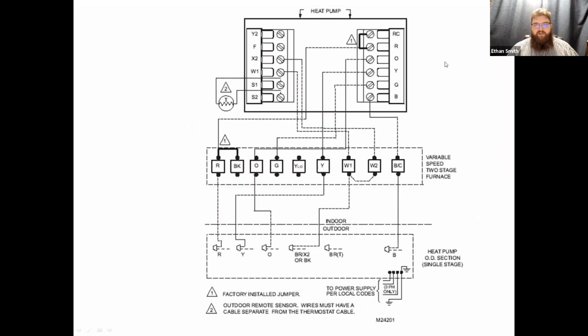Okay, so there's an example of one of these wiring diagrams for a heat pump. This came out of the thermostat wiring diagram. It's typically, like I said, the best place to go. You'll notice a couple unique things. We've got our furnace, we've got our outdoor unit, and we've got our thermostat subbase. Your O terminal is going to come off the thermostat. A lot of times it will land in the furnace, especially in the variable speed models, because that furnace wants to know whether it's heating or cooling, and then it will proceed to the outdoor unit. R, Y, sometimes we'll have a common here. We've got our common wire over on the right.